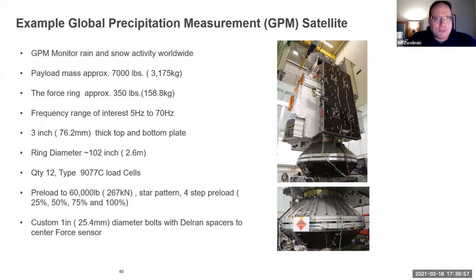Pretty cool, a project we were involved in anyway, from an instrumentation perspective. Obviously, NASA did all the work. We basically talked about the instrumentation itself, but this was an observatory, fairly large, upwards of over 3,000 kg. Certainly the force ring, and what you see here is a head expander or force ring where the force sensors are mounted between this interface here, and you can almost see them in this gap here. So the ring diameter was around 2.6 meters. There's 12 sensors. You've got to preload everything and mount it, custom bolts, and the frequency of interest was like 5 hertz to 70 hertz in this case.